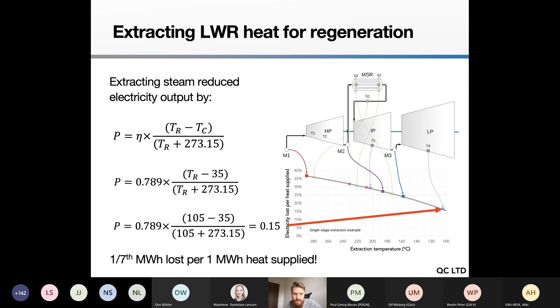Now, if you would like to power the direct air capture system, this is a schematic of how that might look. And this is the regeneration of the sorbent. That's the important part here. So you extract heat out to an external condensing heat exchanger. You condense that steam by heating an external cycle that is heating the direct air capture system. The condensate you are reintroducing into the turbine or the steam cycle at the appropriate feed water heater for that condition. If you have a 3-stage extraction system and you want to get out something like 120 C, it's again about 1 in 7. So you get 1 megawatt hour of heat out usefully for 1/7 of a megawatt hour of electricity lost as an opportunity cost.